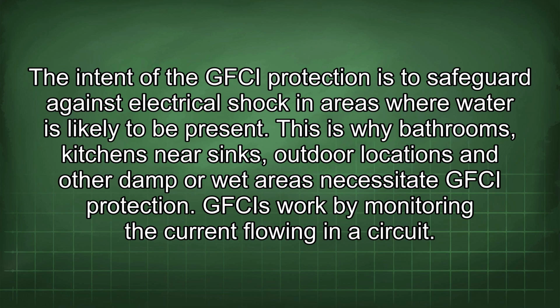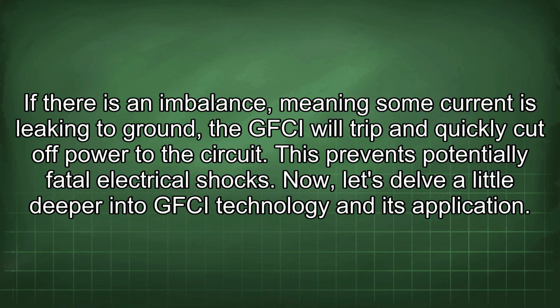GFCIs work by monitoring the current flowing in a circuit. If there is an imbalance, meaning some current is leaking to ground, the GFCI will trip and quickly cut off power to the circuit. This prevents potentially fatal electrical shocks. Now let's delve a little deeper into GFCI technology and its application.